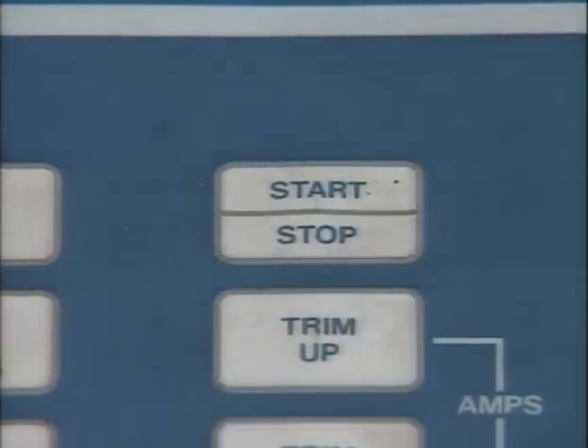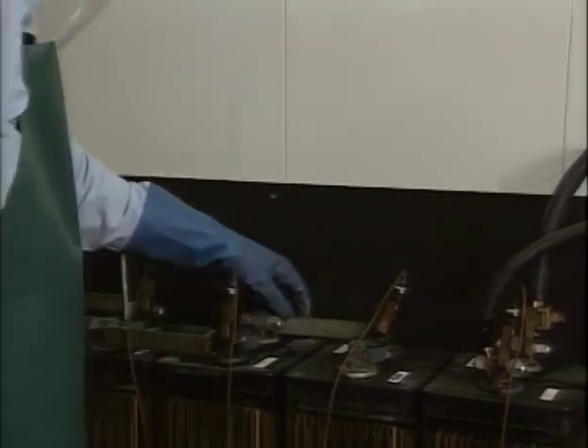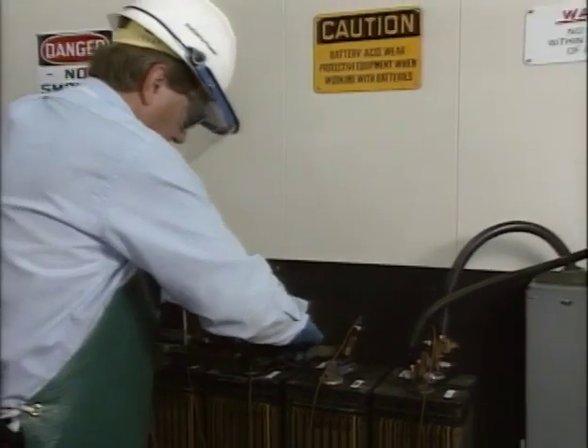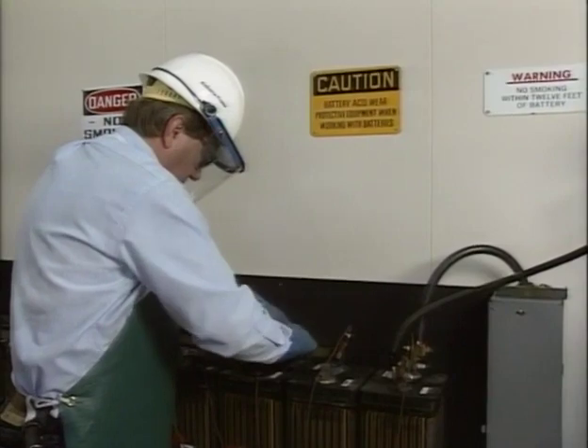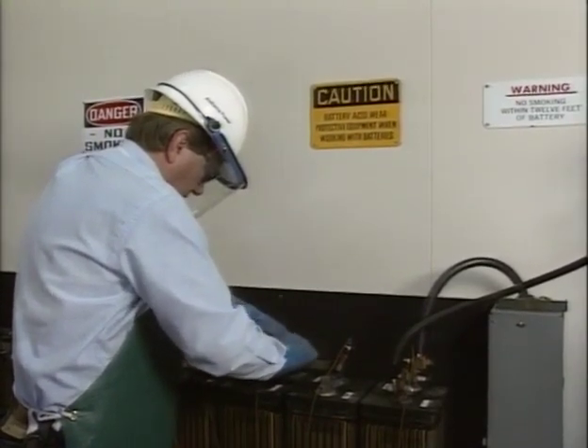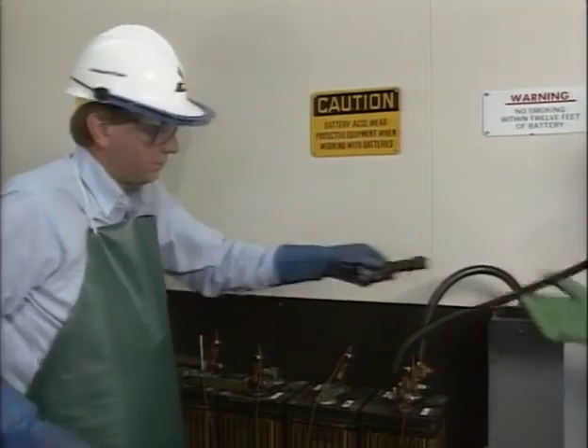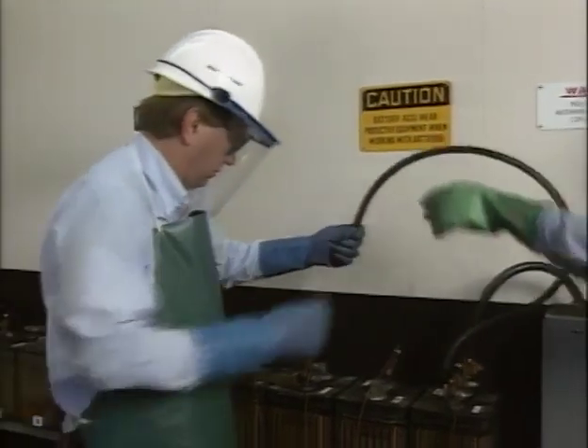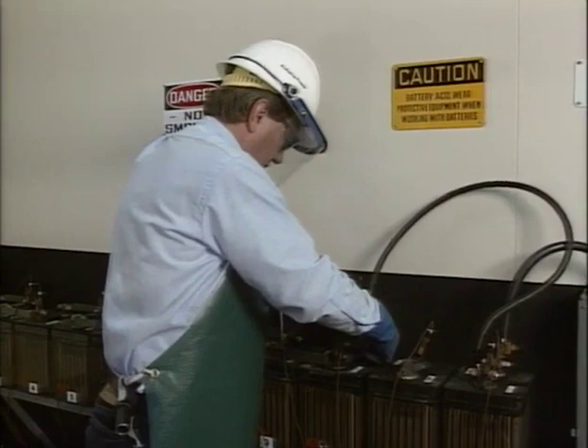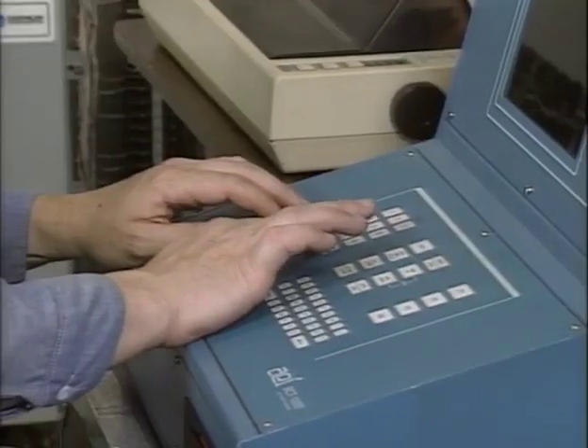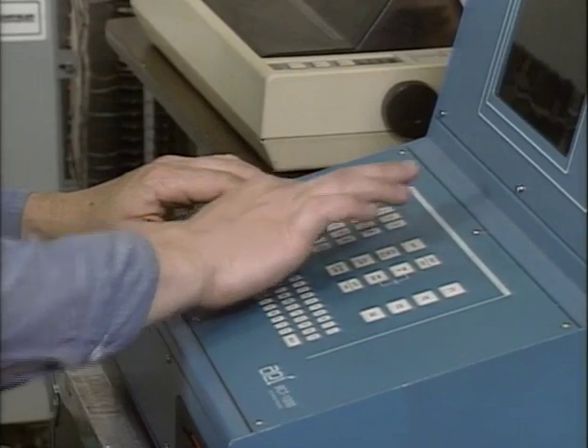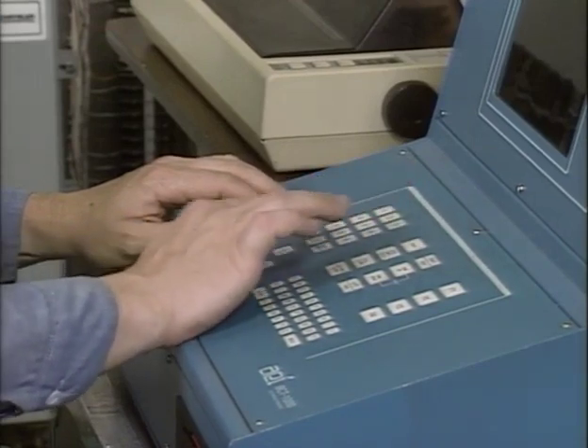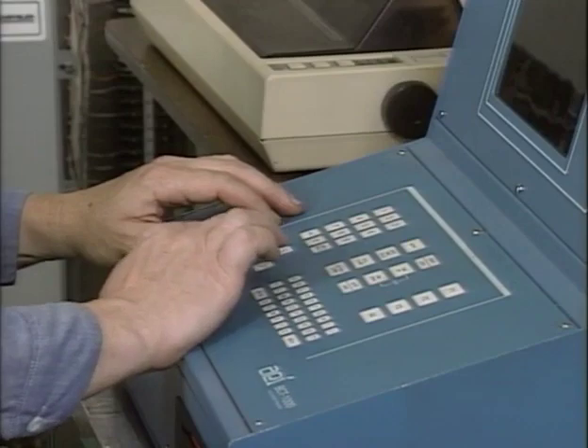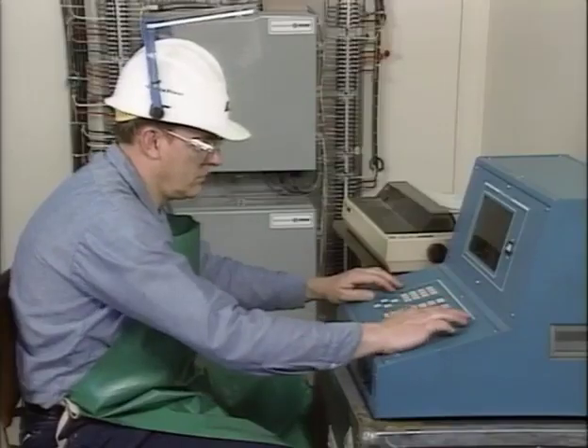If a cell drops to 1.75 volts, the test should be temporarily interrupted. Then the weak cell is disconnected from the battery following the appropriate procedures and bypassed with a jumper. The cell is bypassed because once a cell reaches 1.75 volts, the voltage will drop off quickly. If it drops below 1 volt, the cell may reverse polarity and will be ruined. The low battery voltage value that was programmed into the control unit must then be reduced by 1.75 volts for each bypassed cell, and the test is continued.